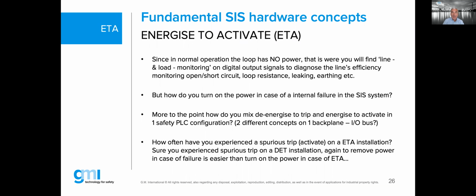But if you lose the line here in an energized to activate, you may not know this without the line monitoring. And that is where you may see the end of line resistance, end of the line, to try to measure that you have still the line there, that you don't have an open circuit, that your loop resistance is still correct, that you don't have leaking, that you don't have earthing problems, etc., etc. But specific, all those items like the open, loop resistance, leaking, earthing, those are the items that we want to diagnose.